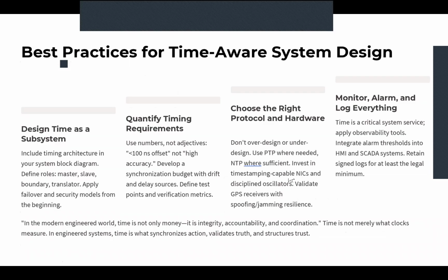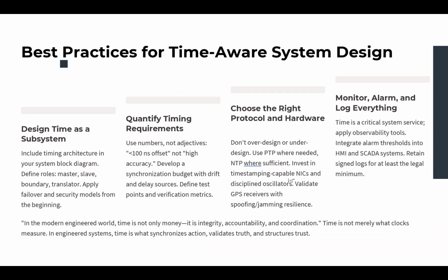Now, what is the best practice for time-aware system design? In traditional systems, timing is normally treated as a passive background, or sometimes assumed to work unless it fails. But IEEE 3044 challenges that view. This means that in your system block diagrams, you must explicitly define the master clock, all the slave clocks, boundary clocks, the time transport medium, which could be fiber or Ethernet, and redundancy paths.